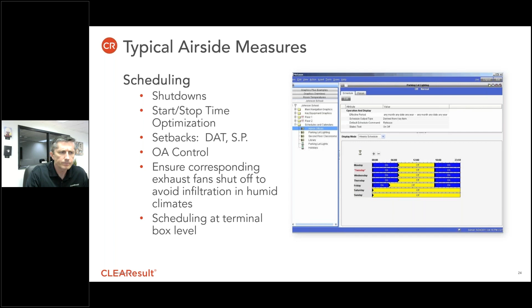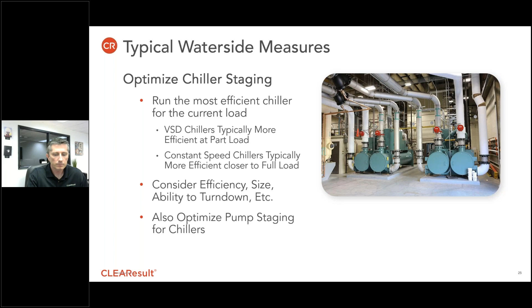On the water side, one common measure is optimizing the staging of chillers. Chillers provide chilled water for cooling to spaces, air handling units, and other equipment. In a large facility with multiple chillers, we want our most efficient chiller at that particular load to be utilized, minimizing energy consumption while still providing the needed cooling.